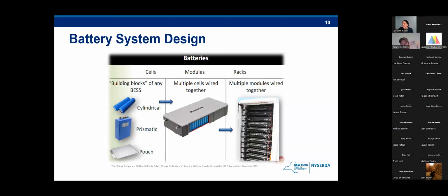So continuing on, we're going to talk more about electrochemical batteries. This slide is really meant to just demystify what we're talking about when we talk about batteries. Energy systems usually consist of three components. First is the cell, which is considered the building block of the energy storage system. These tend to be very small, like the size of AA batteries or something that's in your cell phone or your TV remote. When you start stringing cells together, you get what's called the module. And then when multiple modules are wired together, that creates the battery rack. So in the end, the battery racks are really just a bunch of smaller battery cells wired together to create a larger unit. That's also why you see a lot of these energy storage systems come in different sizing, because there is a lot of flexibility when designing the system, depending on how large of a project they need.